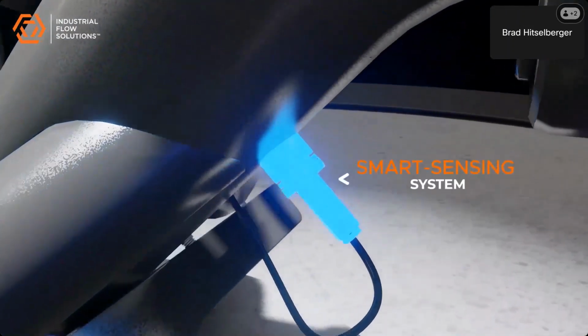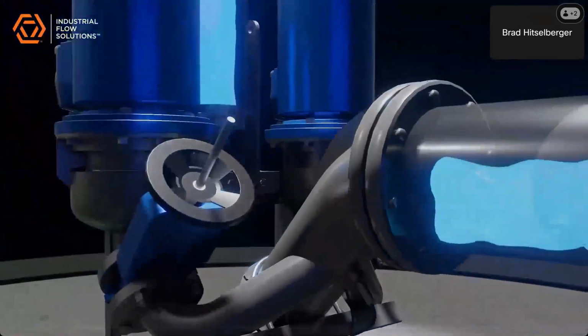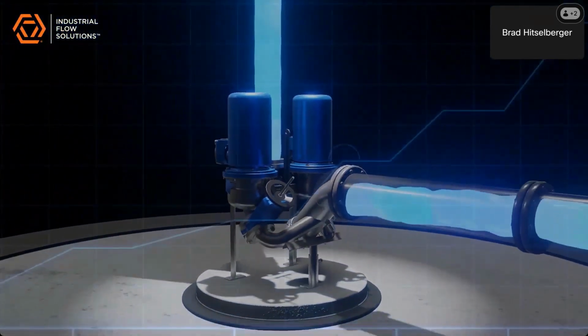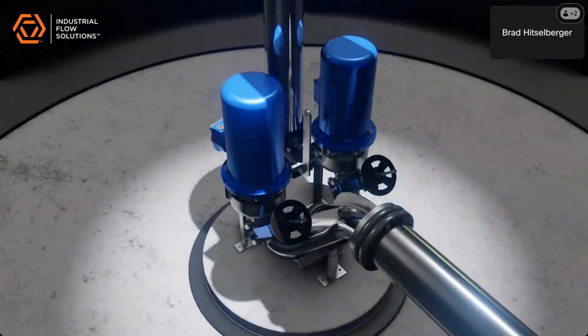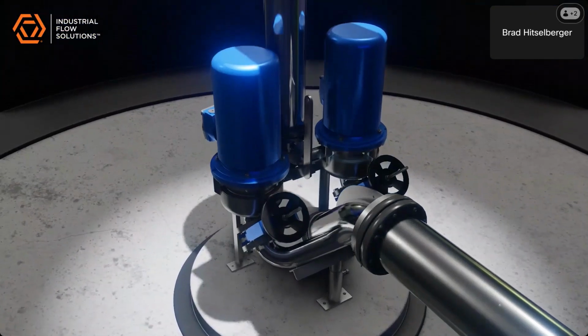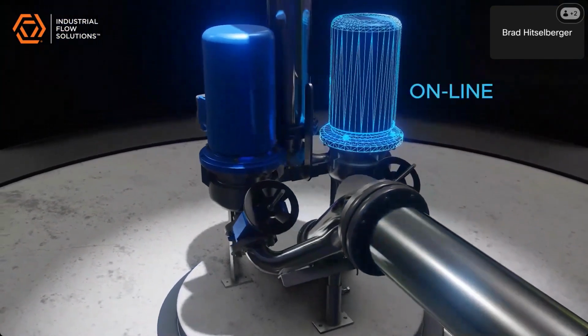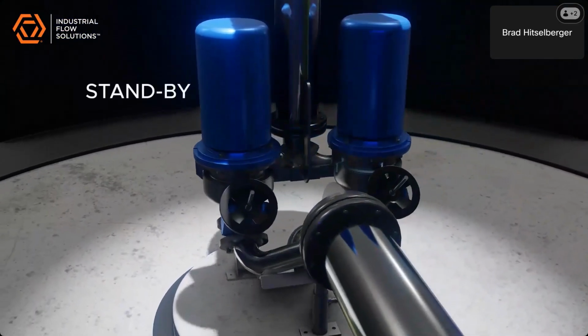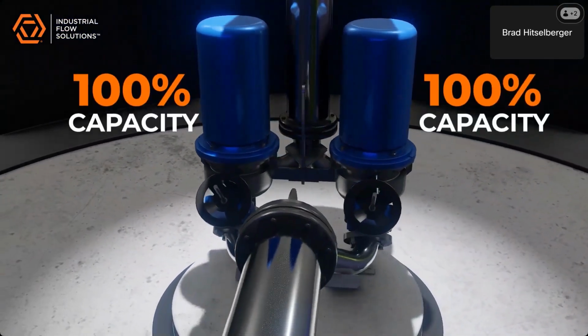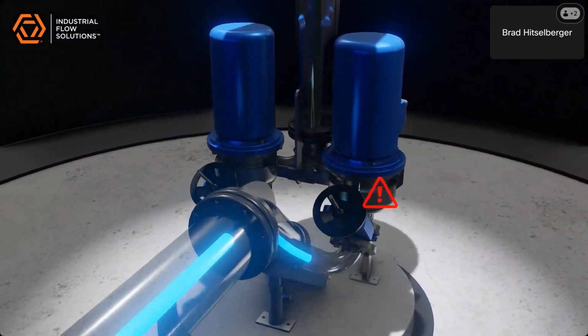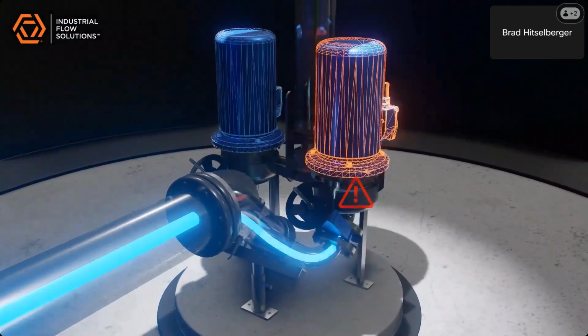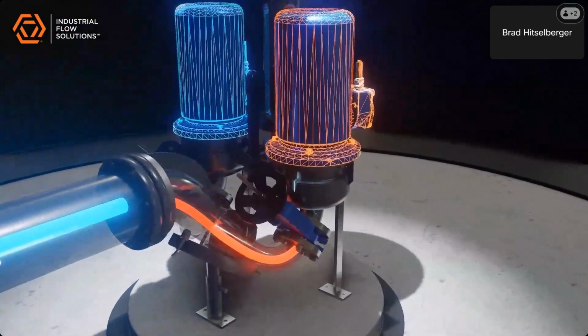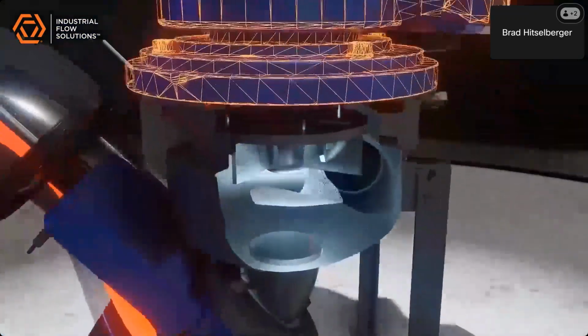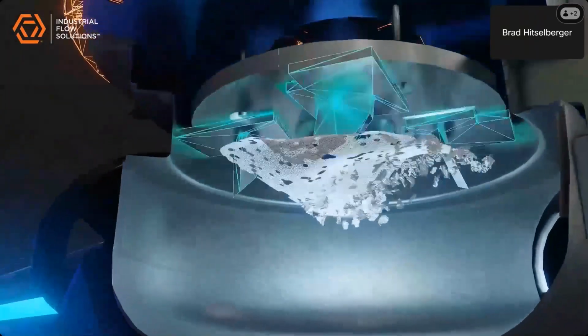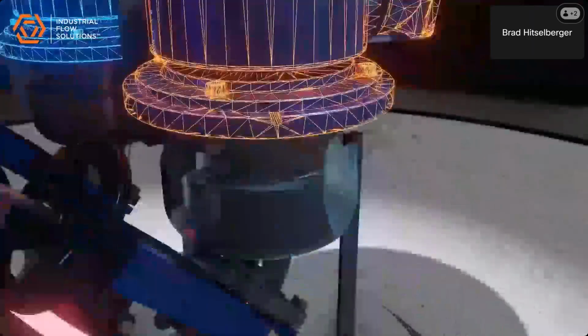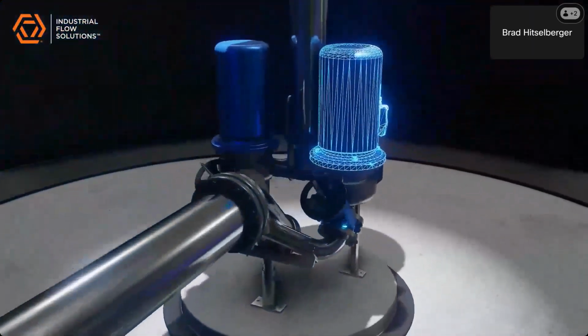The OverWatch smart sensing system adjusts in real time to manage flow and avoid clogs, guaranteeing uninterrupted operation. In the duplex configuration shown, the OverWatch allows for complete redundancy with one pump online while the other pump remains on standby. Both pumps are sized for 100% capacity. When the system detects increased torque due to a clog or rag obstruction, the flow is directed from the online pump to the standby pump. The pump facing the obstruction is reversed, deploying the depth cut impeller shredding blades to clear the blockage. The pump returns to normal operation when acceptable torque is measured.